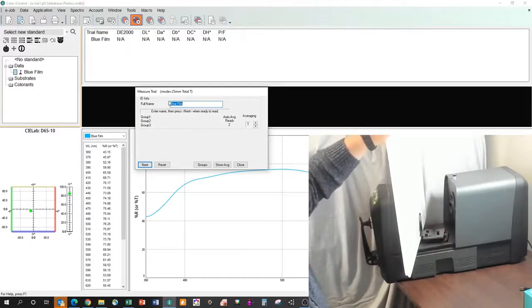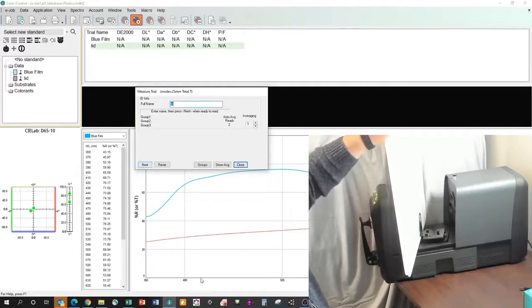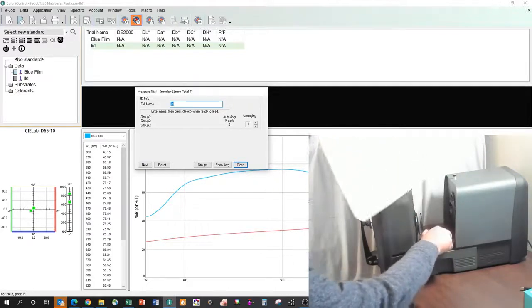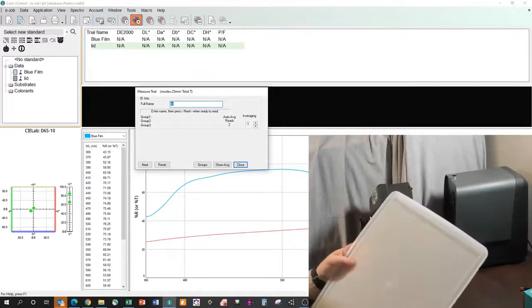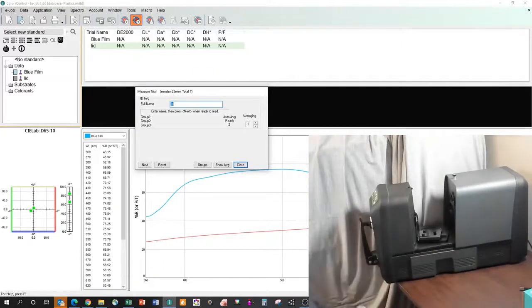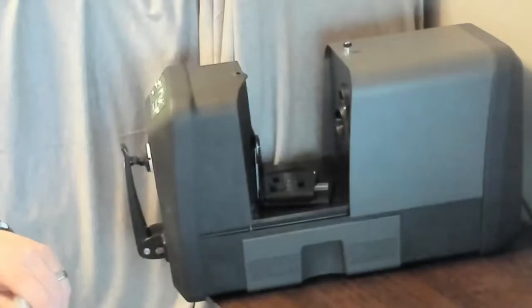We'll just call this one lid. We'll hit next, and we're going to go ahead and measure that. And now you can see the lid has a very different transmission curve than the blue does, because it's nearly clear. But it's that easy for us to do transmission measurements. Likewise, as we saw in the kit, we have the ability to do liquid measurements. If we had liquids loaded in the cuvette there, same process, same procedure. And that's how we do transmission measurements with the Ci7600 series of benchtop devices.